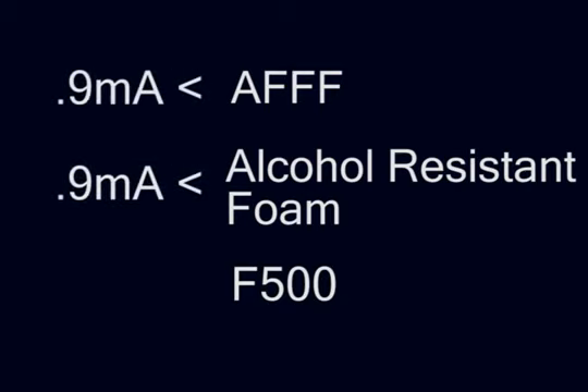Along with the FDNY, we looked at the products available on the market and chose three: AFFF, alcohol-resistant foam, and F500 encapsulating agent. Preliminary testing was conducted at the Fire Academy using a disconnect switch energized to 50,000 volts. The current leakage values from the AFFF and alcohol-resistant foam exceeded the established safety limit of 0.9 milliamps, but the F500 agent produced leakage values similar to that of water, which we already knew to be safe.